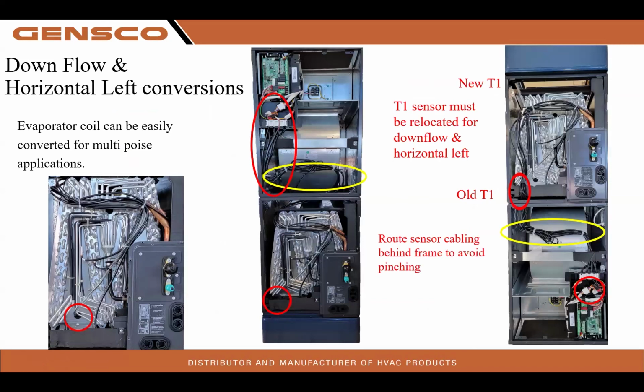Downflow, horizontal left conversions. Evaporator coil can be easily converted for multi-position applications. Very simple. The only time that we're going to need to make some adjustments here is if we're going to go downflow and horizontal left. All we've got to do is remove T1 return air room sensor right here and put it up to here. We will reroute the sensor cabling behind the frame to avoid pinching.